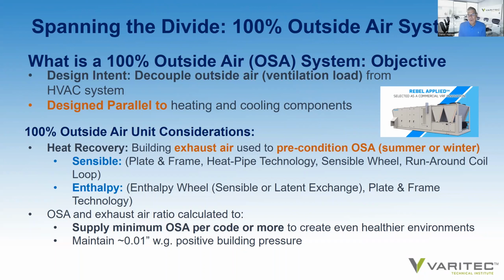And there are two ways you can do that. You can provide a heat recovery solution that handles the sensible load. That is the amount of energy in the space or building as measured at a thermostat, or enthalpy, which is the total load, which is comprised of the sensible load as well as the energy that holds water in a vapor state, otherwise known as humidity levels.